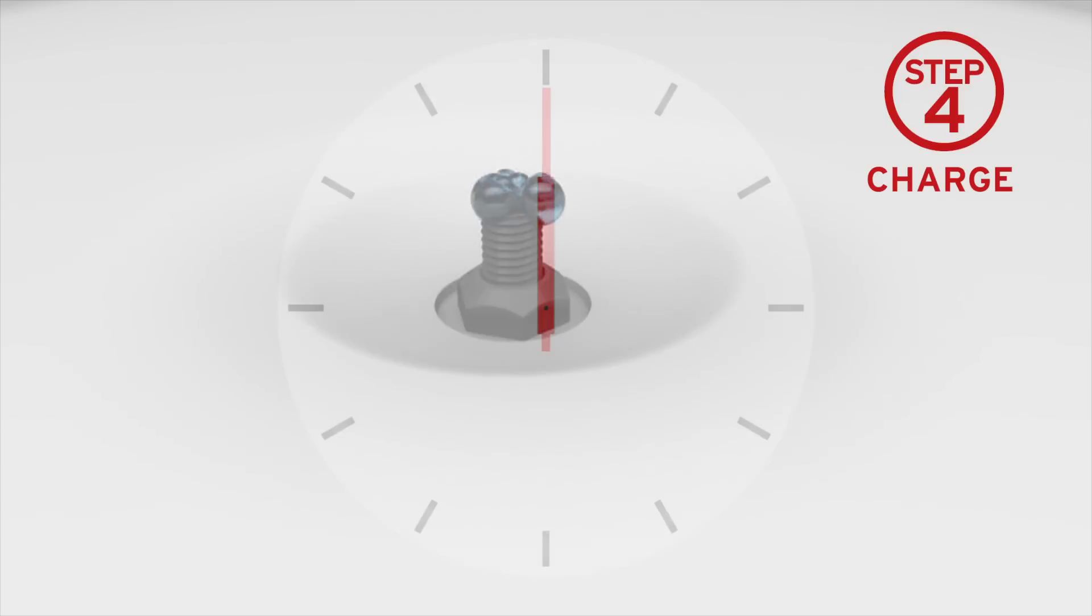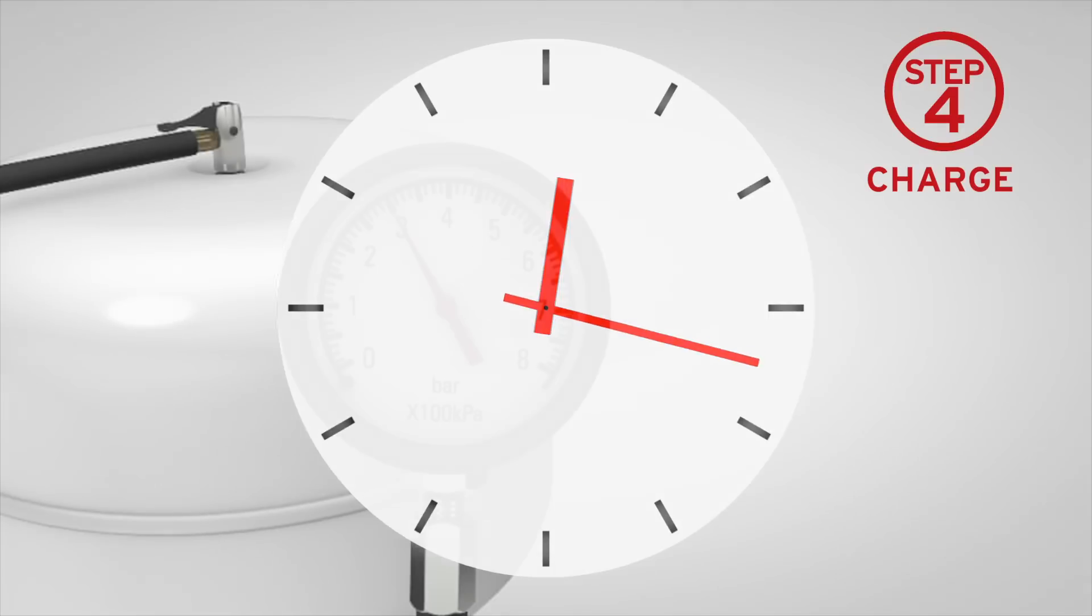Step 5: If a leak is found, replace the expansion vessel. Assuming no leak is detected, leave the vessel for a minimum of 20 minutes and retest to ensure the valve is holding charge.